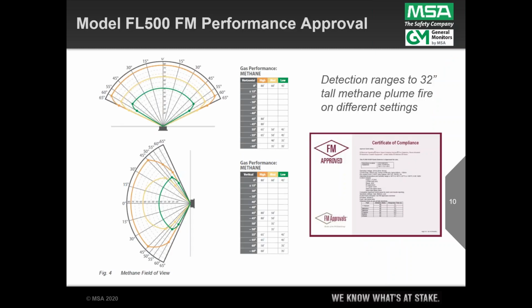And I just wanted to quickly show the FM, the Factory Mutual. This is the standard 3260 certificate of compliance, and it shows that the FM audited the performance claim by MSA, GMI, of the FL500, and this just shows you the field of view diagrams that they validated that we've got on high sensitivity to a 32-inch tall methane plume. We get 80 feet on high, 60 feet on medium, and 45 feet on low.